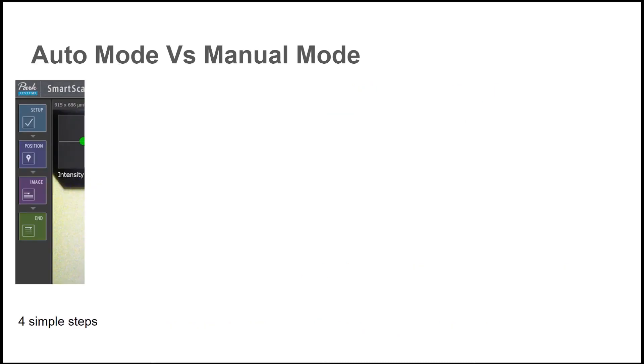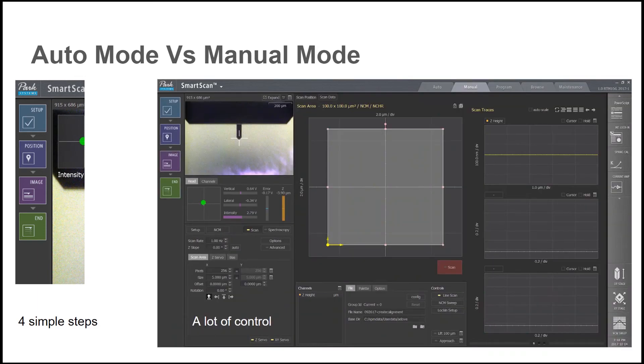The Park AFM has two modes: manual mode and auto mode. Auto mode has four simple steps — setup, position, image, and end — while manual mode has a lot of control. You actually have access to those four buttons on the manual control page, but you may operate the tool from either tab.